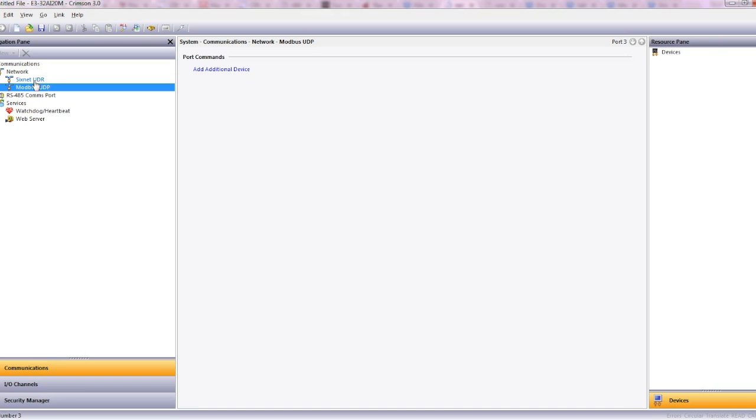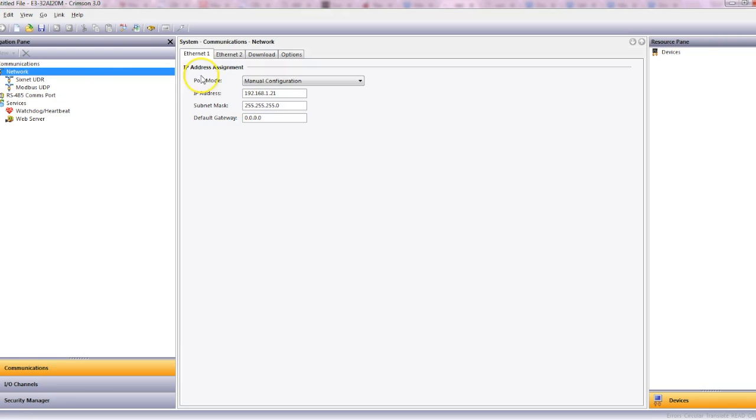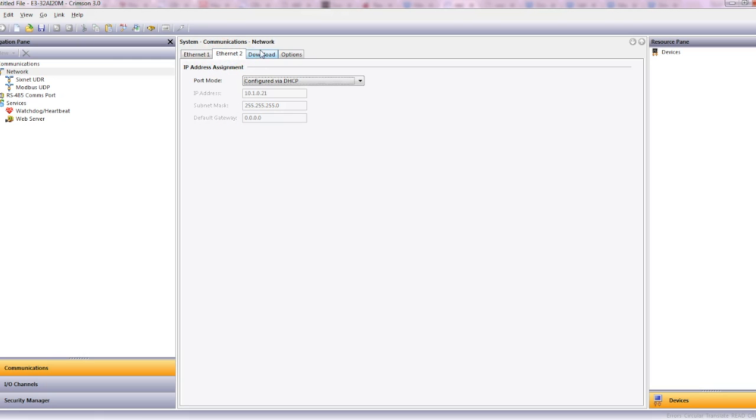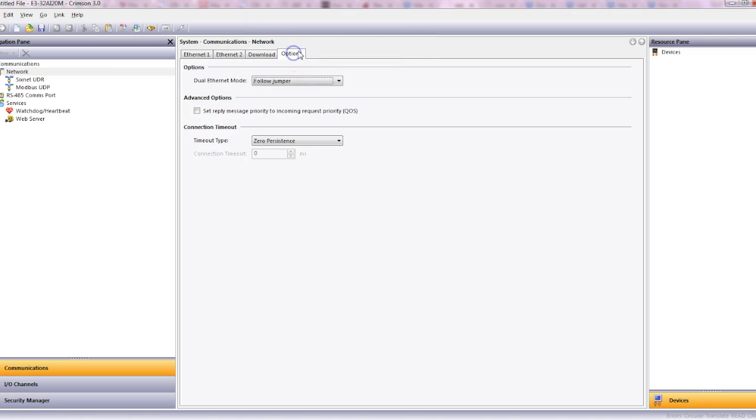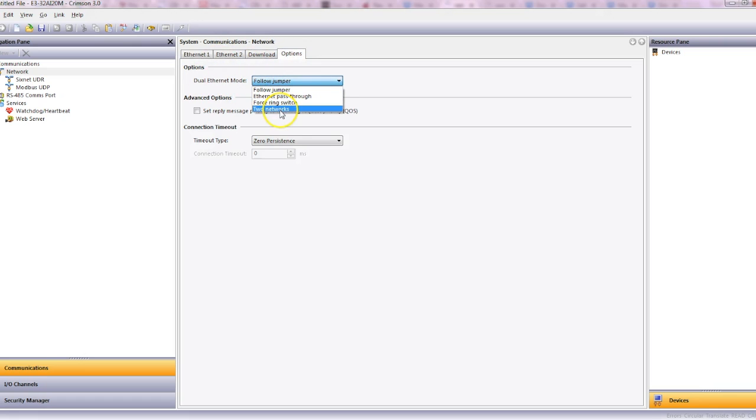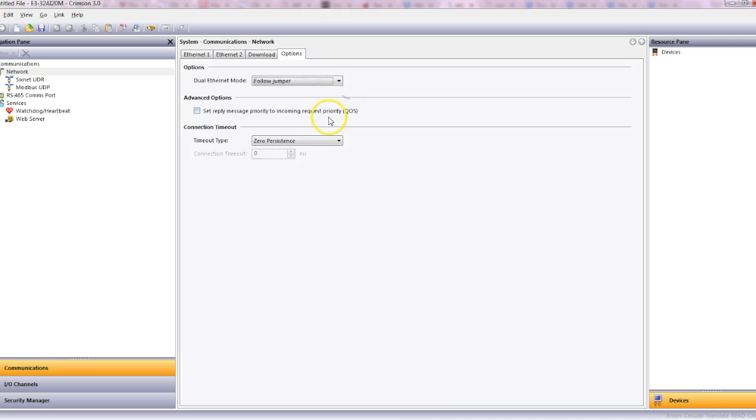Inherently it's a slave, so that's great. There's no setup need to be done, just configure our IP address. We've got Ethernet port 1, Ethernet port 2 if desired. The download is automatically enabled so we can download via Ethernet. Then we've got options, which sets up the dual Ethernet port on how it responds, whether it's two networks or forced as a ring switch. We're going to leave the jumpers as the default.